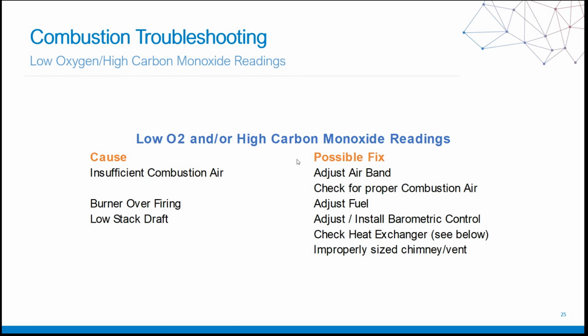I'm going to go over a quick 30-second check at the end of the presentation to show you, on a forced air system, how to check for a cracked heat exchanger with a combustion analyzer. The last thing we want to check if we have low stack draft is, do we have an improperly sized chimney or vent? Are we using the correct size piping for our termination? Did somebody change it prior to you getting there?